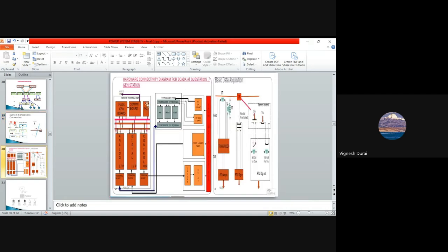This is again hardware. This is the switchyard equipment, field equipment, where your PT and CT are there. Through that, you will connect to a transducer. The transducer's output will go to our analog to digital converter, from your RS 232 port communication protocol. Something they will use, anything they will use. But this is the overall hardware connectivity for SCADA at substation level.